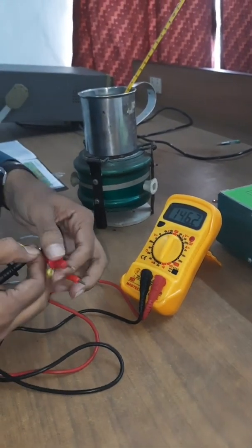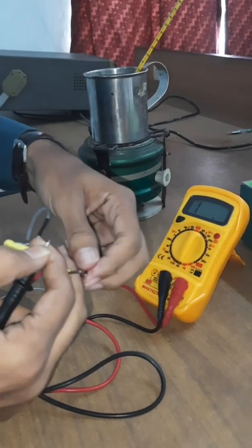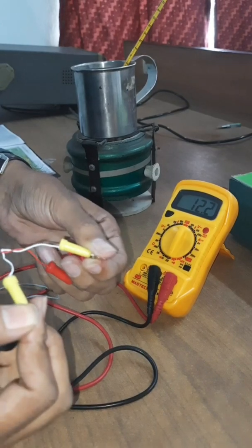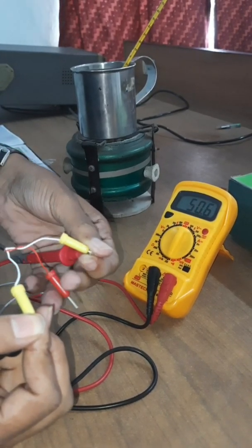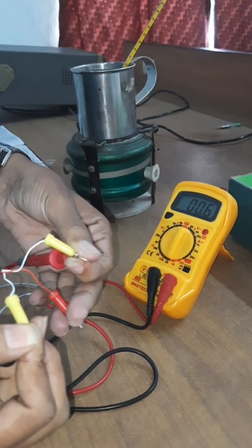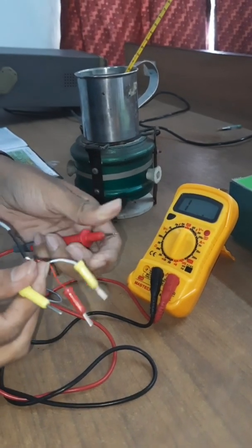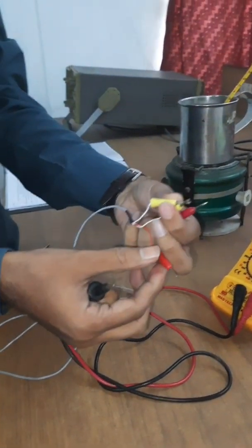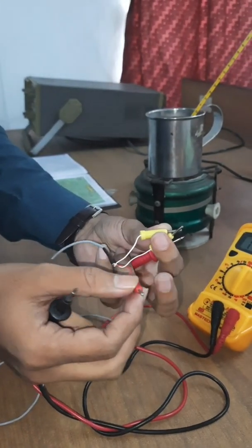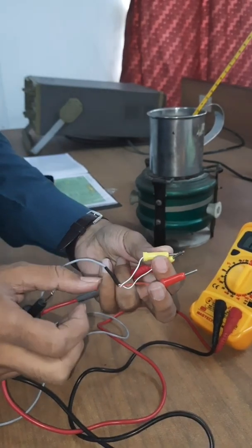Just to show that these two white windings, these are nearly shorted. We are trying to find out the resistance of these two white windings. And you will find that this is very very close to zero. Essentially, these two are short circuit and you find the resistance between the red and the white and this forms the resistance of the RTD.